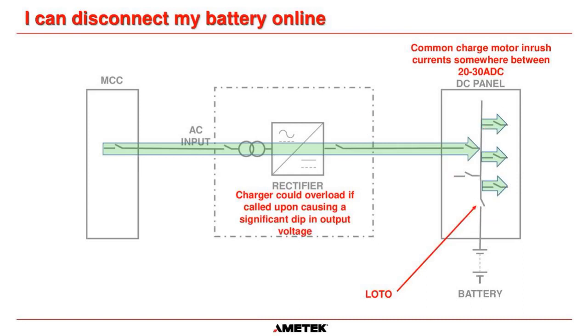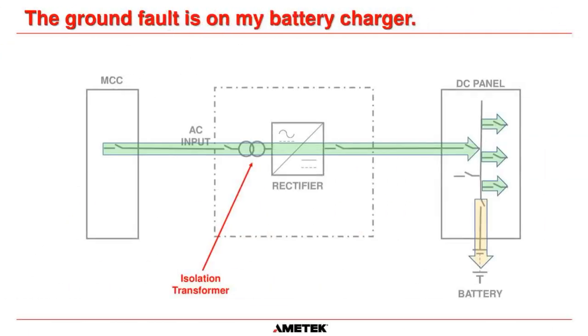John's asking a good question. I thought the point of using this configuration was so you could remove the battery for maintenance. That's on a dual parallel system. For this system here, to answer your question, if you were going to take this battery out of service, you could either tie in a temporary battery into this point here, or because you have a free disconnect switch here, you could tie in a temporary battery into there, close this disconnect, and then open that disconnect, and then the temporary battery would give you backup while you do work on that battery. It was the dual parallel system that allowed you to take one system offline, not a single system. Okay, I hope that explained that.